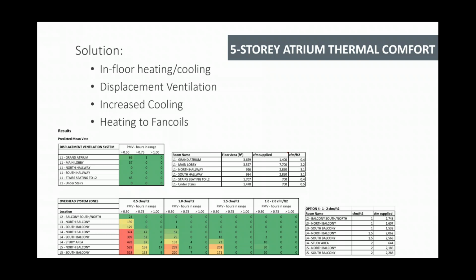Along with that, in terms of the thermal comfort analysis that we did, part of the solution was in-floor heating and cooling on that main floor area with displacement ventilation. And as per the charts here, increased cooling and heating to the fan coils around the perimeter as well. Those fan coils are only on levels 2 and up, so the main floor is cooled strictly with the in-floor system and displacement ventilation. It was interesting that our thermal comfort model helped drive the design of that area.